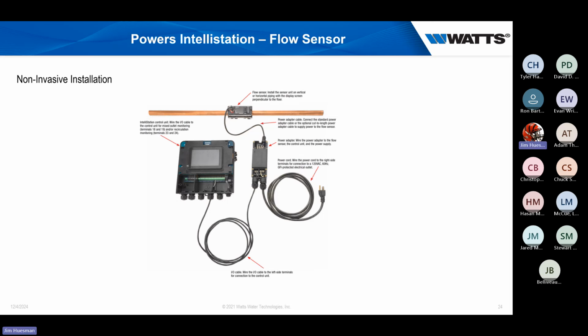I really do like this flow. Working with hospitals, a lot of times when these are sized, they take a total fixture count, and from that we're trying to figure out what's going on with the system and why we're having issues. A lot of times when we're able to add in that flow sensor, we're able to actually see real data of how much water is being used on any given day, any given hour. We're able to relate that back to troubleshoot. I've had a couple where the copper was pitted out so bad, and it turned out it was undersized with a lot more flow than intended.